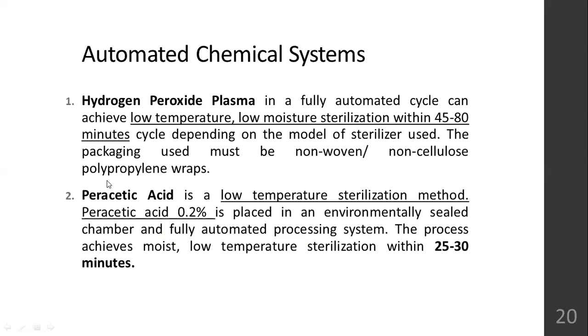Next is automated chemical systems, hydrogen peroxide plasma. It is a fully automated cycle where you can achieve low temperature, low moisture sterilization within 45 to 80 minutes of the cycle. Okay. So here, this model of sterilizers are used. Again, in here also packaging is required. Polypropylene wrap or non-cellulose wraps is to be used to wrap the instruments and then do the sterilization. Because these things work at very low temperature, low moisture, okay, they take time to do the sterilization.